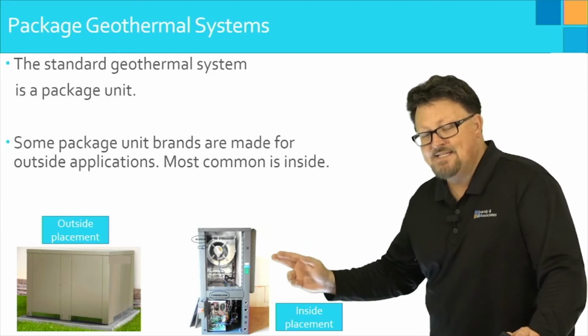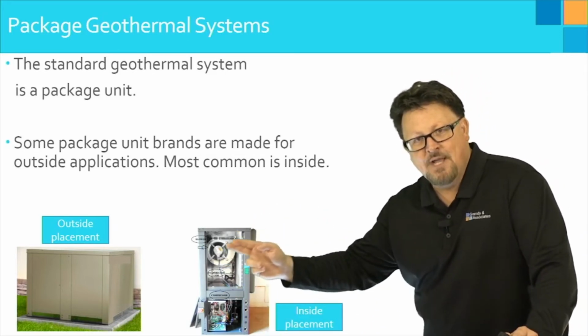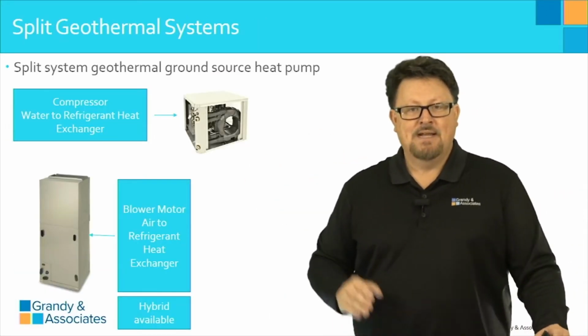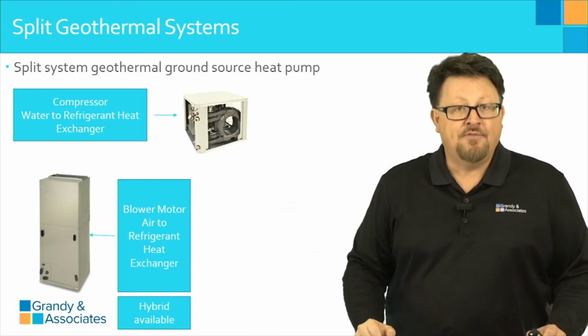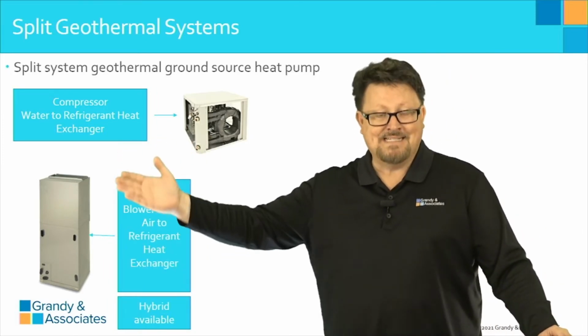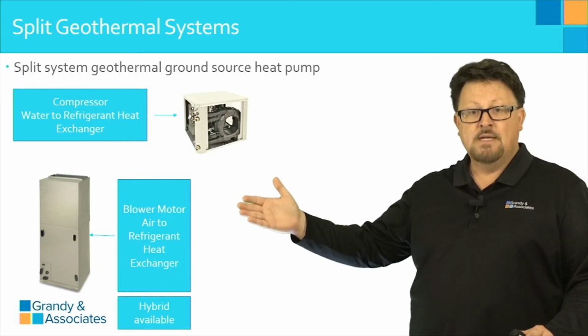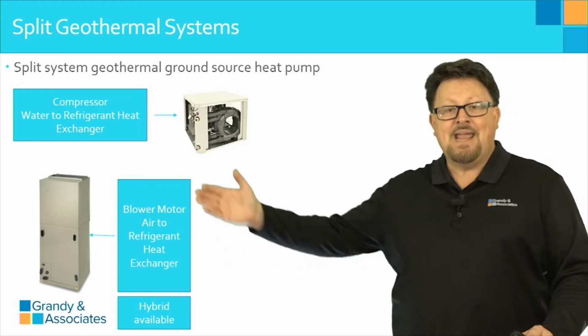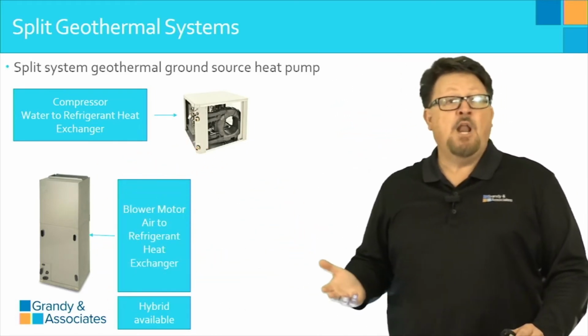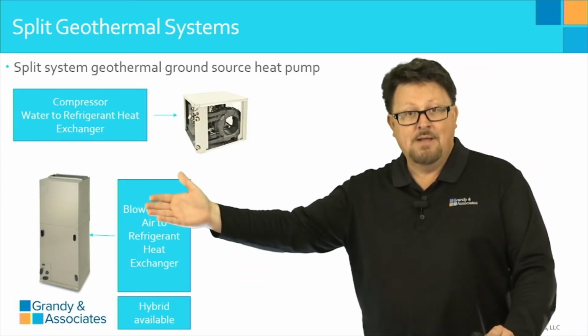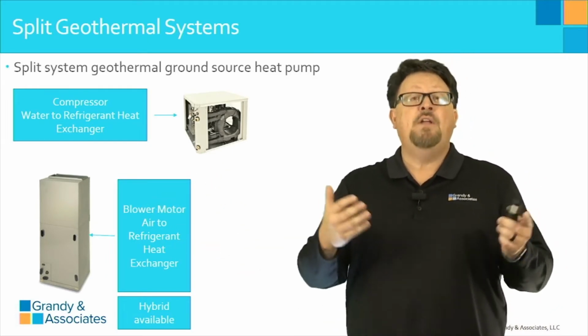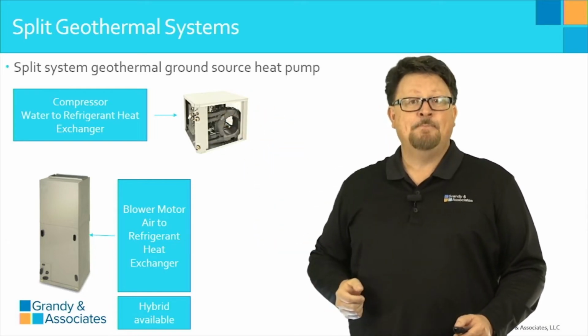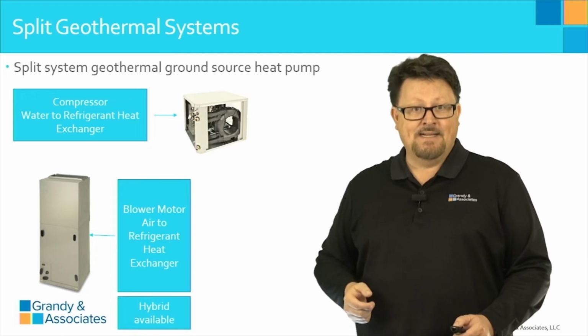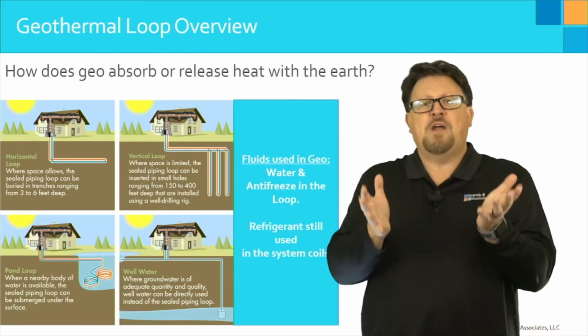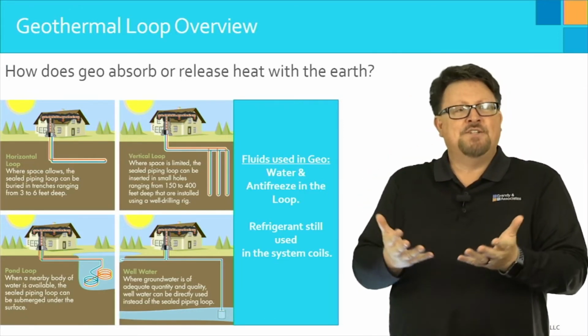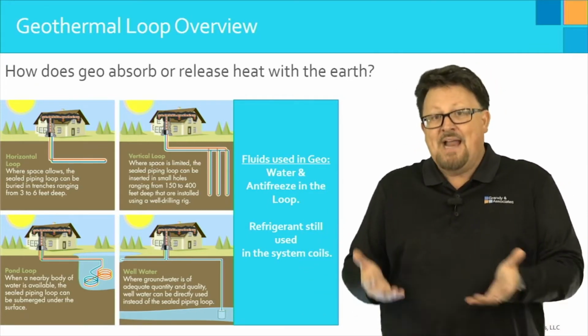Basically, what this split system does is take the components that are in the standard package unit and divide them into two sections. In the smaller section, you have the compressor and water to refrigerant heat exchanger. In an air handler designed to work with geothermal application, you have the blower motor. You also have the air to refrigerant heat exchanger in this particular piece of equipment. Something a lot of people don't realize, hybrid options are also available in a split system geothermal option, so that in very, very cold temperatures, you could have that nice warm heat from natural gas or other options at those designated times. So as we're looking through this, the big question everybody always has: how on earth does a geothermal system absorb or release heat with the earth? That is how it's distinctly different.